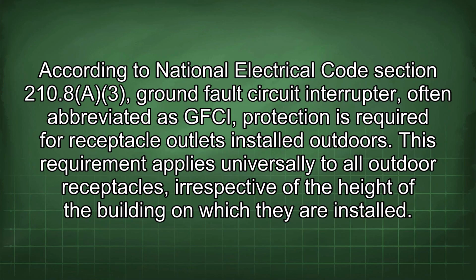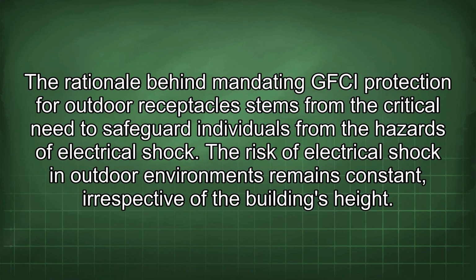According to National Electrical Code Section 210.8A3, ground fault circuit interrupter, often abbreviated as GFCI, protection is required for receptacle outlets installed outdoors. This requirement applies universally to all outdoor receptacles, irrespective of the height of the building on which they are installed. The rationale behind mandating GFCI protection for outdoor receptacles stems from the critical need to safeguard individuals from the hazards of electrical shock. The risk of electrical shock in outdoor environments remains constant, irrespective of the building's height.